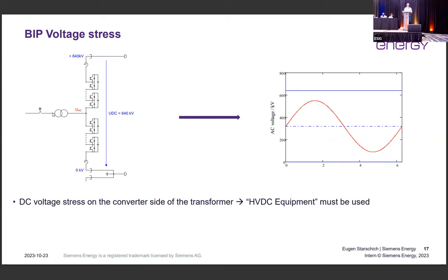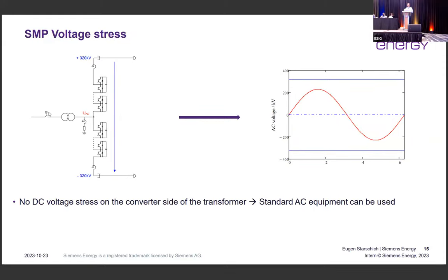One of the main influences is on the transformer: as mentioned before, we need a specific transformer. There is not so much other AC equipment, but there is a pretty big impact on the offshore applications. All the offshore converters used so far for transmitting power from offshore wind to land are symmetrical monopole. To make a very compact converter design, you use GIS systems. It's very easy to use on the AC side, because you don't have a DC voltage offset.